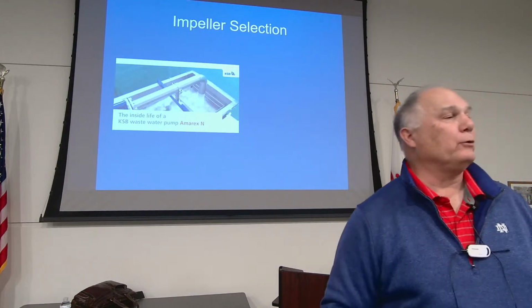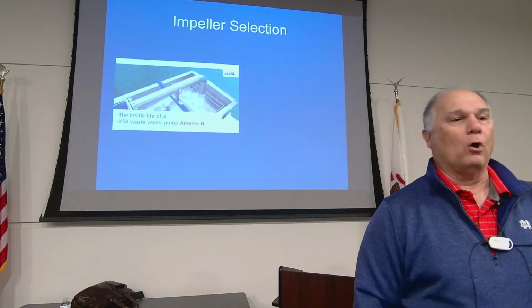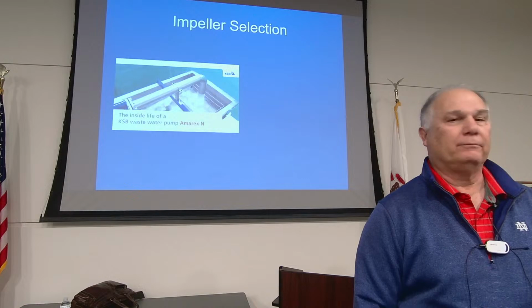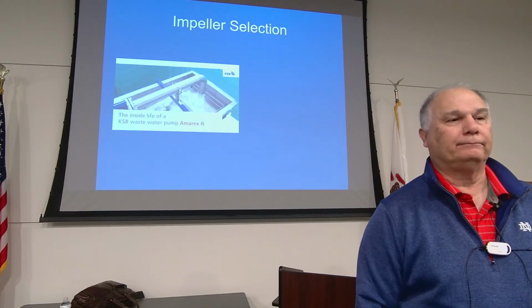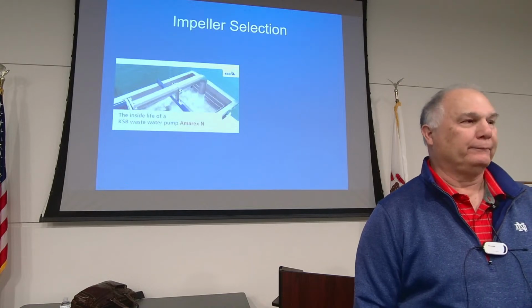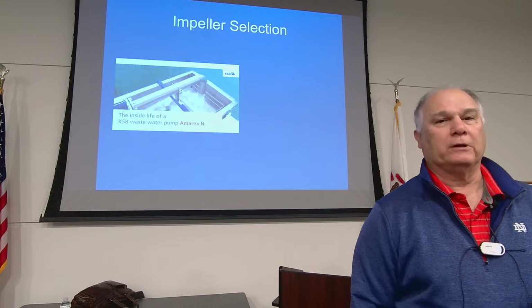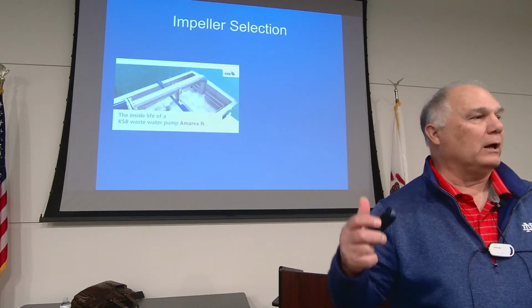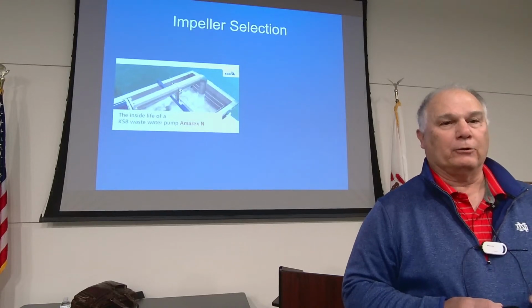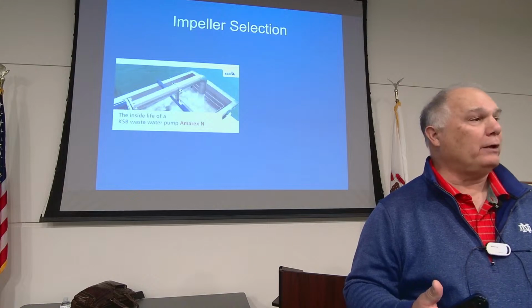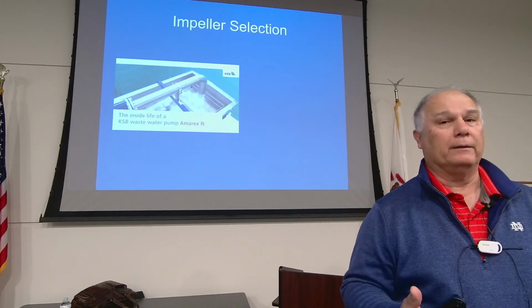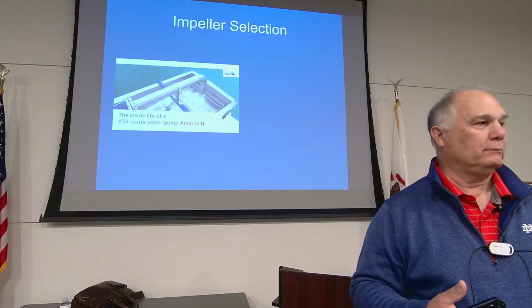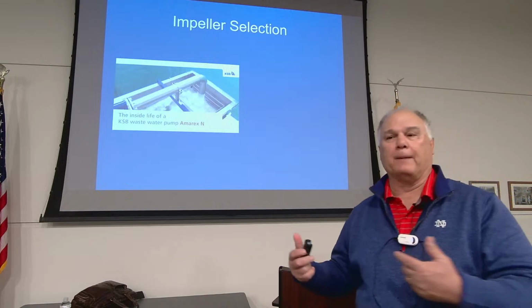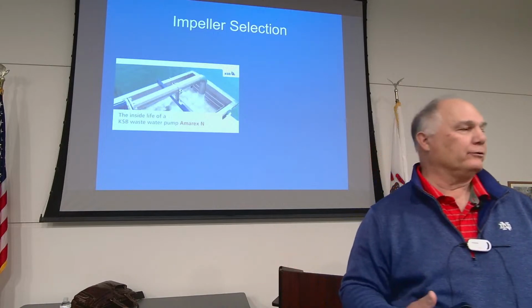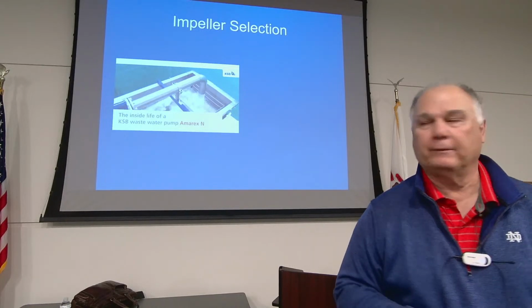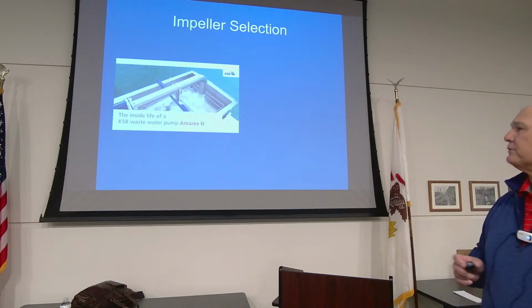So that's grinder pumps. So if you have a 4-inch diameter pipe or bigger, what type of pump should you use? Should you use a grinder pump? No, don't use a grinder pump. Do yourself a favor. If you're going to have a 4-inch diameter solid or 4-inch diameter pipe, use a non-clog or a solid handling pump. Grinder pumps may be a little less expensive in their capital costs, maybe, but they are much higher on O&M cost. Therefore, you'd be better off using a properly designed, properly installed, non-clog or solid handling pump for anything that's 4-inch and larger. So when we talk about 4-inch and larger, this is a Vortex impeller pump.